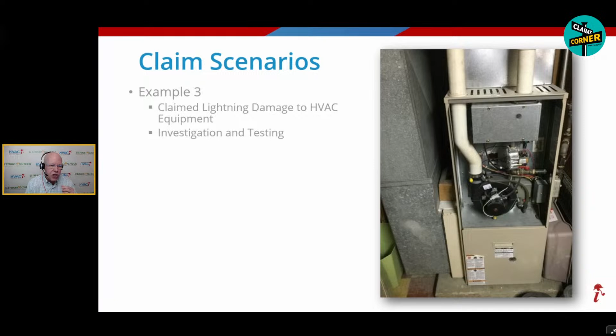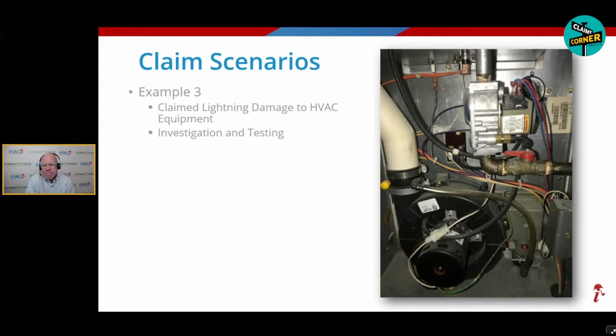So if you see a plastic exhaust flue, you know you're dealing with high efficiency. And the reason you need to know that, it costs more to fix or to replace. So make sure you know whether it's high efficiency. So there is one of those draft inducer motors. See the gas valve there, low voltage again, testing all that stuff out. In this case, it looks okay. No damage to the high efficiency furnace.